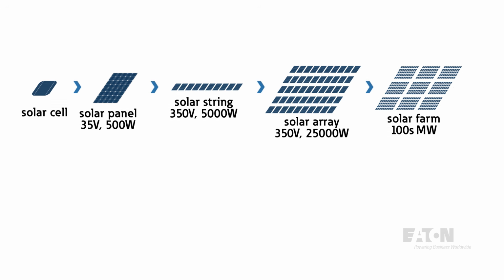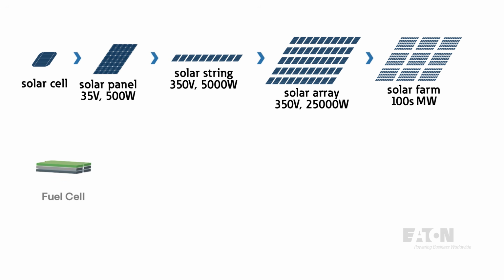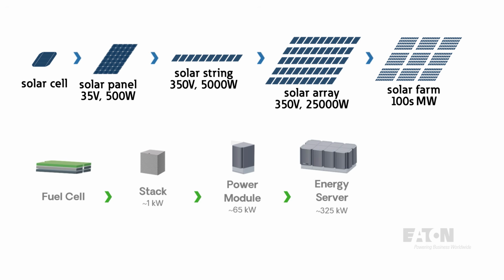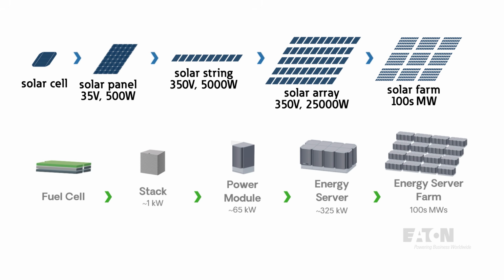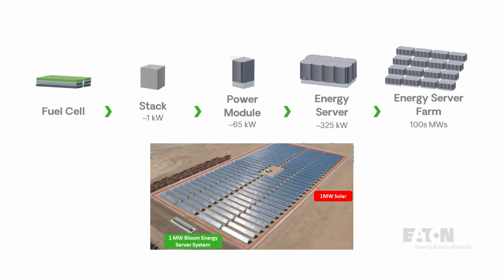With fuel cells, we start with a 1 kilowatt stack of the individual fuel cell components. Then we combine the stacks into 65 kilowatt power modules. Next, we connect several modules in parallel, and for example, 5 of them, or 325 kilowatts, may be connected to one inverter. These modules plus the inverter are called an energy server. Multiple 325 kilowatt energy servers together like this make a server farm and can be several megawatts or several hundred megawatts.